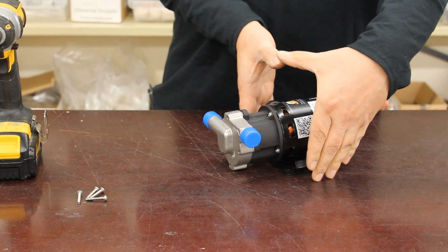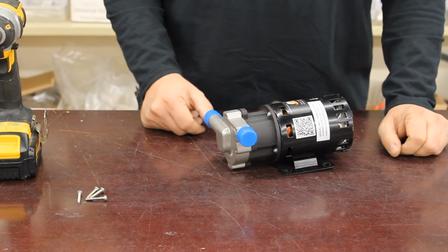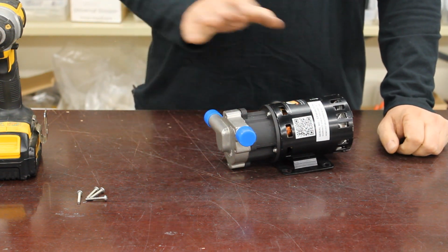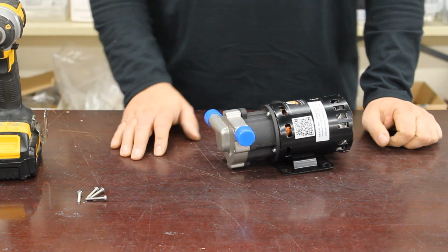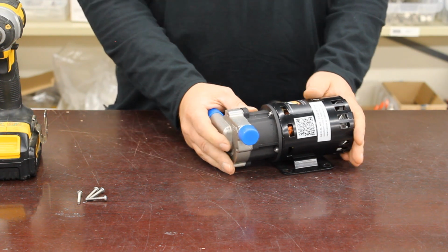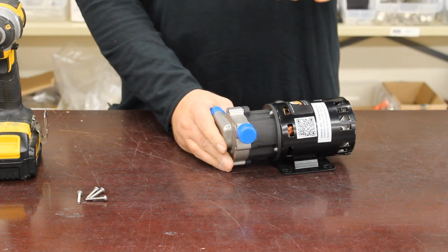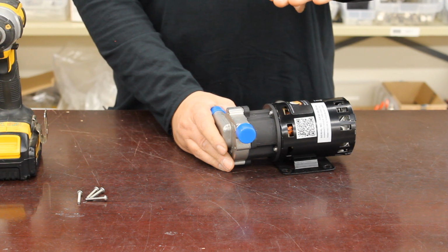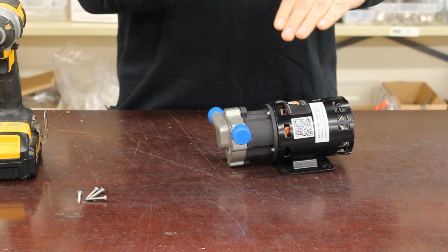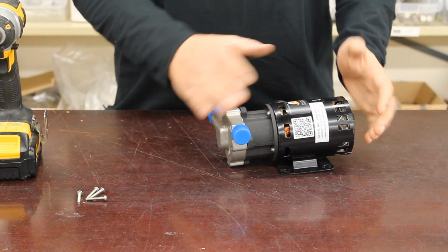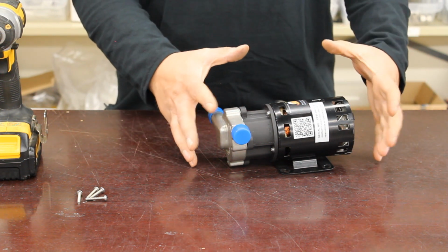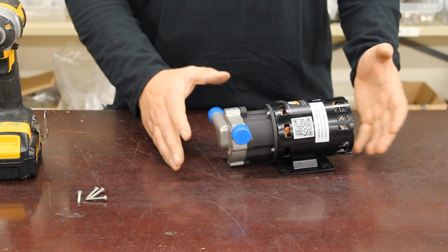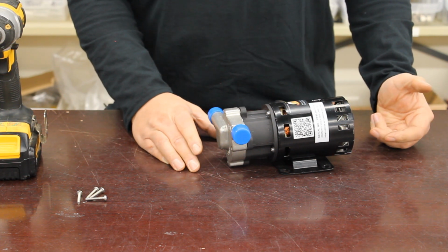Please do not put coffee can shaped shrouds around these pumps. That's definitely a problem. Also, mounting these pumps too close to burners, for example a banjo burner slamming six inches away from the pump, with all the heat reflecting off the bottom of the pot, creates a pillow of really hot air right around the motor where it's trying to vent and keep cool.